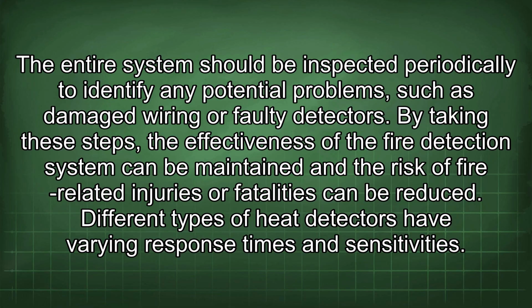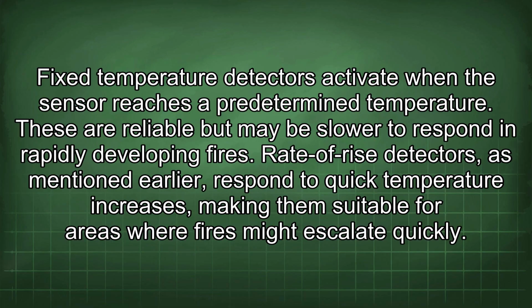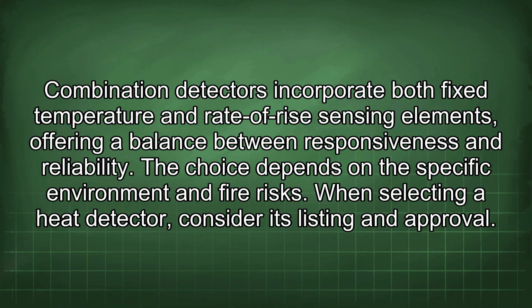Different types of heat detectors have varying response times and sensitivities. Fixed temperature detectors activate when the sensor reaches a predetermined temperature. These are reliable but may be slower to respond in rapidly developing fires. Rate of rise detectors, as mentioned earlier, respond to quick temperature increases, making them suitable for areas where fires might escalate quickly. Combination detectors incorporate both fixed temperature and rate of rise sensing elements, offering a balance between responsiveness and reliability. The choice depends on the specific environment and fire risks.